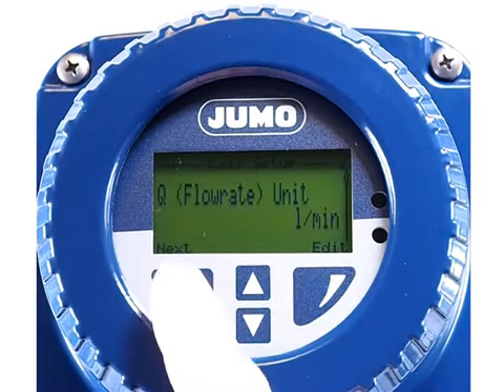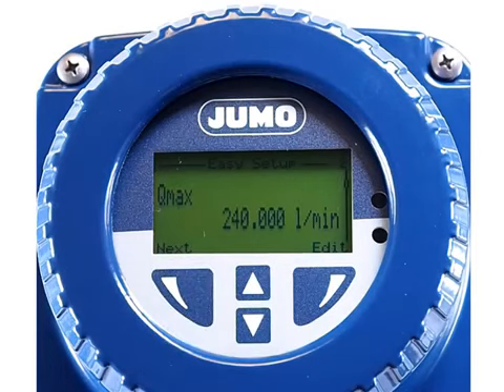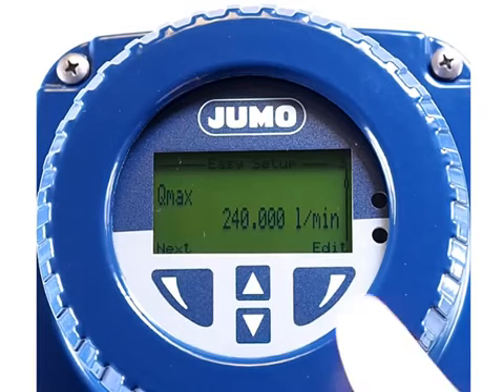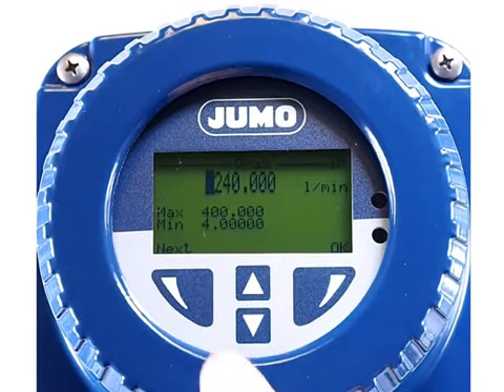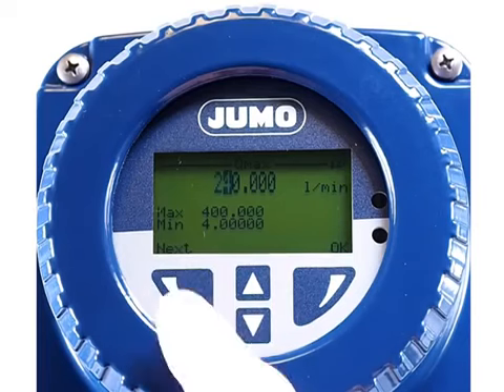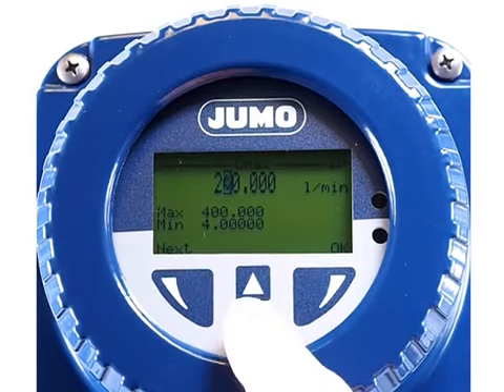We decide on liters per minute. Thereafter, the measuring range is set. This value corresponds to the maximum current output of 20 mA. This value is used for scaling the signal for further processing in a field device such as a controller or a recorder. So the value set here also needs to be set in the field device. The known capacity of 12 cubic meters per hour would correspond to 200 liters per minute. To make sure that the value is not exceeded, we decide on 240 liters per minute.